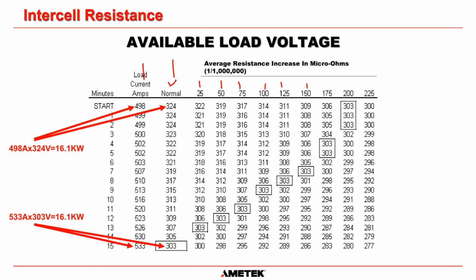columns are is what the voltage would be if the average resistance of the intercell connections increased in microohms, okay? So what they're saying is if the intercell connections on the battery only increased by 25 microohms, which is a very, very small amount, then the voltage dropped across that higher resistance will mean we will get to our end voltage of 303 volts quicker, at the 13-minute mark. So we're not going to get as much capacity out of the battery.